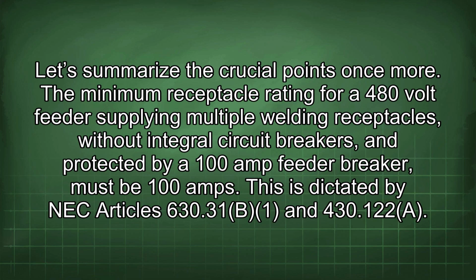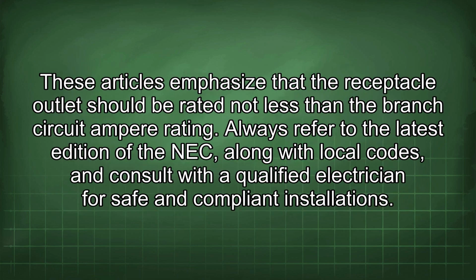Let's summarize the crucial points once more. The minimum receptacle rating for a 480-volt feeder supplying multiple welding receptacles without integral circuit breakers and protected by a 100 amp feeder breaker must be 100 amps. This is dictated by NEC Articles 630.31 and 430.122(A). These articles emphasize that the receptacle outlet should be rated not less than the branch circuit ampere rating.